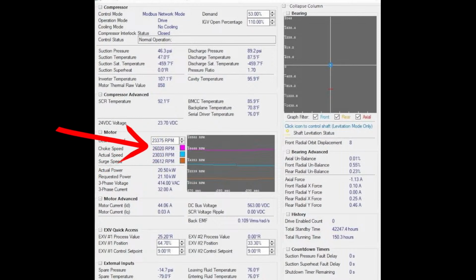And what's being referenced here is the choke speed, actual, and surge speed. And you'll notice the surge speed is lower than the choke speed. And okay, so why is that? Well, the choke and surge values are all based off of this pressure ratio up here, which is the compression ratio. They just reference it as pressure. So this pressure ratio is dividing the discharge pressure by the suction pressure.